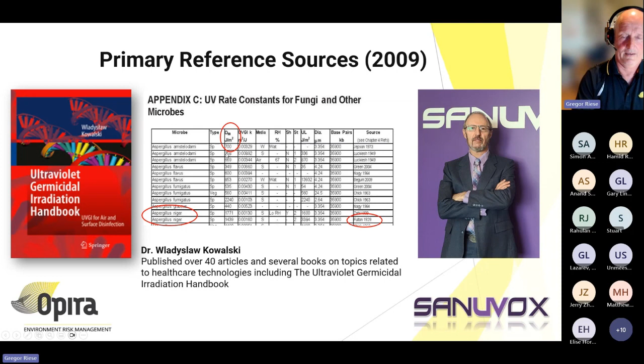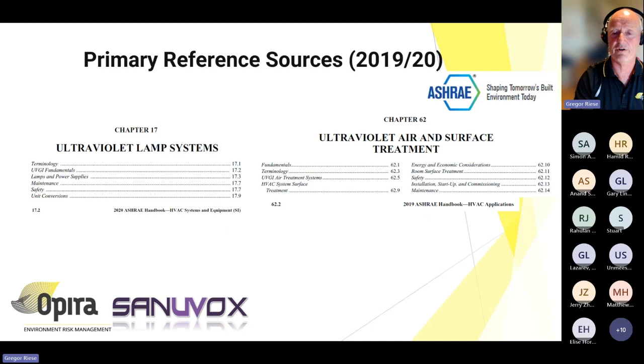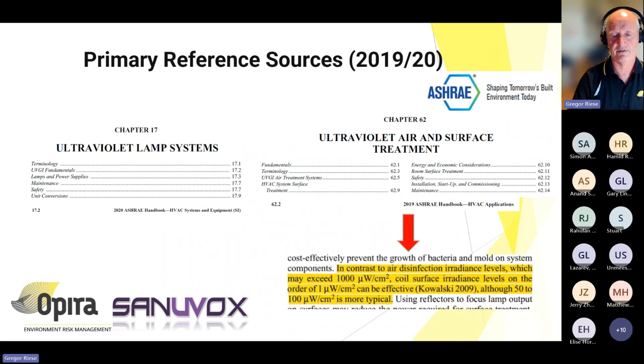Then we go on to ASHRAE, and these are the two ASHRAE publications that I alluded to earlier. These are really important publications, and they don't actually tell you how to size up systems in terms of dose, but they give you a very good guide, and particularly one section of chapter 62 of the handbook specifically mentions that 1 microwatt per centimetre squared can be effective in front of a coil face in terms of eliminating growth, but typically 50 to 100 is installed.